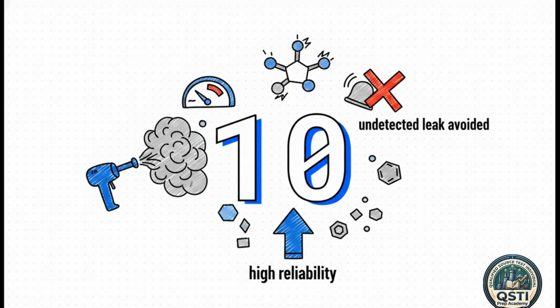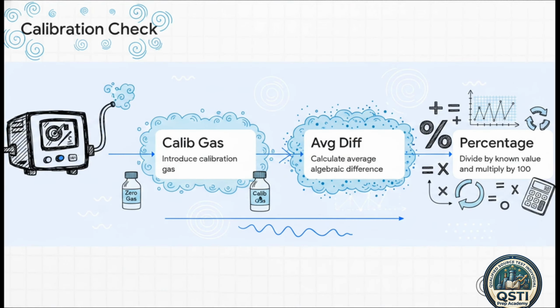Now, the really crucial point here is that this response factor must be less than 10 for every individual VOC we measure. If that response factor is too high, the machine is basically blind to that specific chemical, meaning dangerous leaks could go completely undetected. Keeping this factor under 10 guarantees our readings stay highly reliable across a wide variety of toxic gases. So let's look at how this builds into the precision check. It's a strictly regulated, four-step math routine performed before the analyzer ever goes into service.